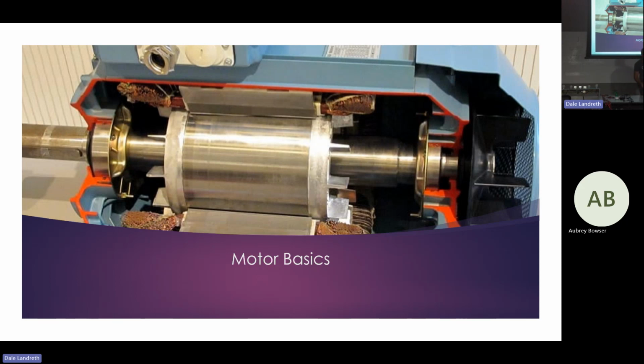It's a simple meter. You basically push a button. I put my leads on the motor windings, set my meter to the Meg-Ohm test. Like Jared said, this one does 50 to 1,000 volts, and I always test at 1,000 volts. Once everything's set up, you push this button, and it puts 1,000 volts DC to that motor.